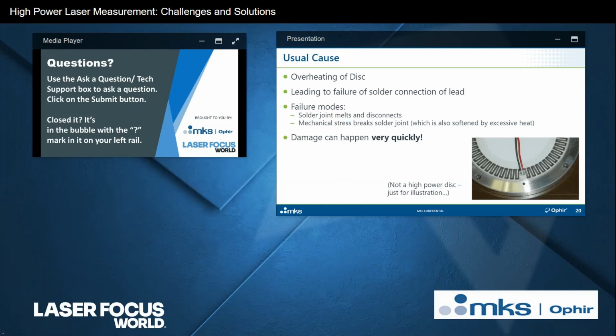So basically, when you have overheating of the disk, the first point of failure is generally going to be that solder connection from which the leads emerge from the sensor to the rest of the instrument. A possible mode of failure might be the connections in the thermopile itself coming apart, but that usually would happen at a much higher temperature than the solder connections of the leads.